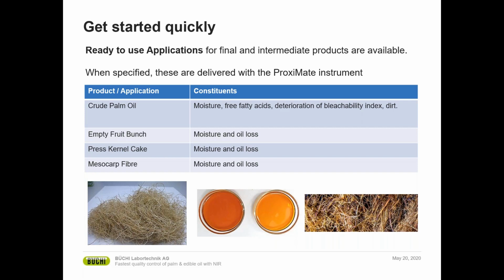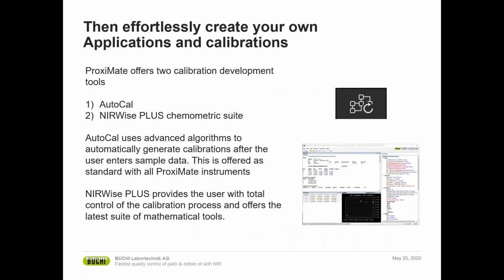Now, as you work with the NIR instrument, you might find that you develop your expertise and you want to develop your own applications with the data that you're getting out of the instrument to even further maximize the value that you're getting from the NIR investment. And we're able to do that using a choice of 2 calibration development tools with ProxiMate. We offer AutoCal and also the NIRWise Plus chemometrics suite. AutoCal basically uses advanced algorithms built into ProxiMate that mean that you only need to enter laboratory reference values to samples that you've already taken in the ProxiMate instrument. And a simple press on the screen allows the ProxiMate to optimize calibrations and applications within ProxiMate to your own laboratory reference analysis, allowing you to develop new applications.